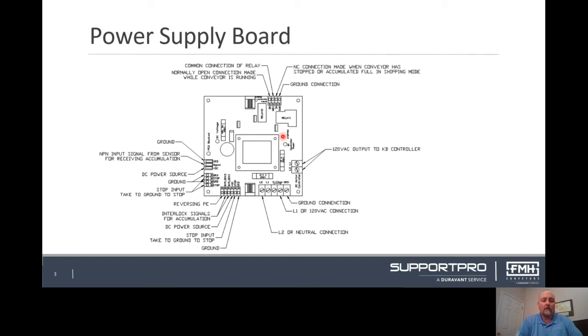If this light is on, check to see if all e-stop buttons are reset and make sure the photo-eye package stop is clear. The F1 fuse or 2 amp fuse controls the control circuit and will need to verify that this fuse is not blown.